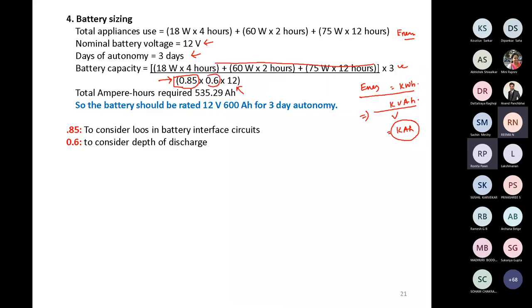Another figure is 0.6. What is this implying? Whatever battery capacity you have, you won't be able to discharge it fully. There is a concept called depth of discharge. For example, for a lead acid battery, if it is 100 ampere hour, you won't be able to discharge it entirely to 100 ampere hour. Maybe you will be able to discharge it up to 50 to 60%. The rest of the capacity is not usable. For lithium ion battery, you can go maybe around 70-80%. The rest of the capacity, though it is there, you won't be able to utilize it. It may damage your battery. You don't want to deep discharge your battery, so there will always be a limit.